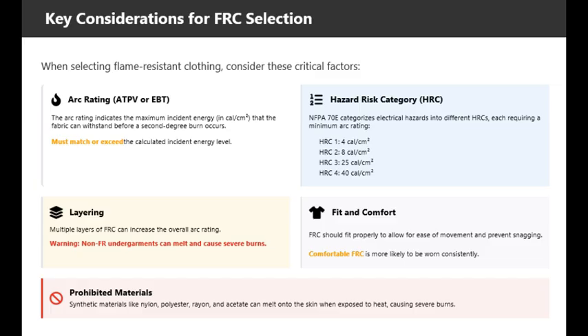The most important factor is the arc rating, expressed as either ATPV, arc thermal performance value, or EBT, energy break-open threshold. The arc rating indicates the maximum incident energy in calories per square centimeter that the fabric can withstand before a second-degree burn occurs. Your FRC must have an arc rating equal to or greater than the calculated incident energy level for your work task.